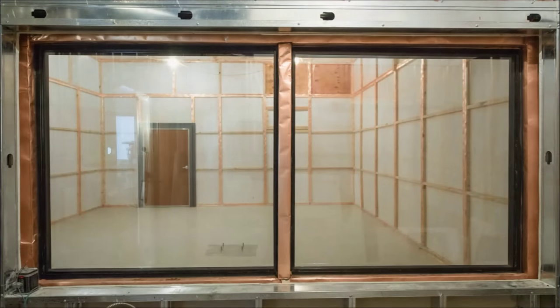As you can see, this process takes tremendous skill and attention to detail. Once the shielded walls are complete, the same type of RF panels are used for the sealing of the enclosure. Openings for shielded doors and windows must be precisely located and installed in the planned structure as it is built.